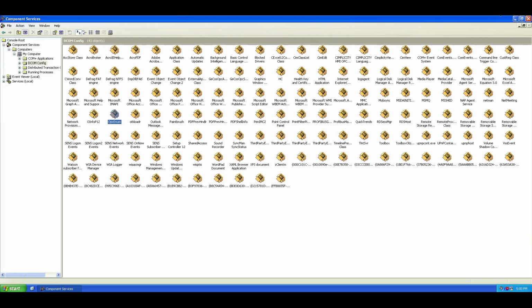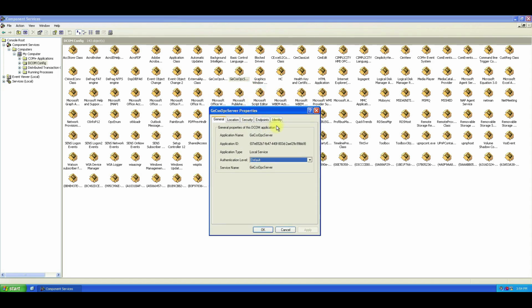Finally, if you want your OPC server to run under a specific user instead of the default system account, find the GeCssOpcServer and change the Logon As setting to the user you want. Then in DCOMCNFG, right-click GeCssOpcServer, go to Properties, and make sure the Identity tab matches that same user.